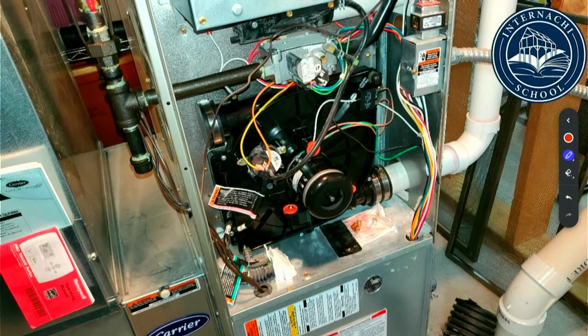We're still going to have an inducer fan. I will say one thing, though, the housing for the inducer fan, if you're not sure what you're looking at, if this housing is made of plastic, then this is a high efficiency furnace. If this housing is made of plastic, then my vent or vent connector has to be made of plastic as well. I can't use metal on these because the corrosion or condensation that comes out of there will eat through that metal in like 2 years or less.